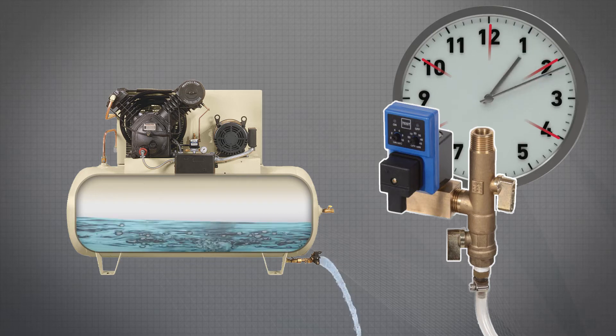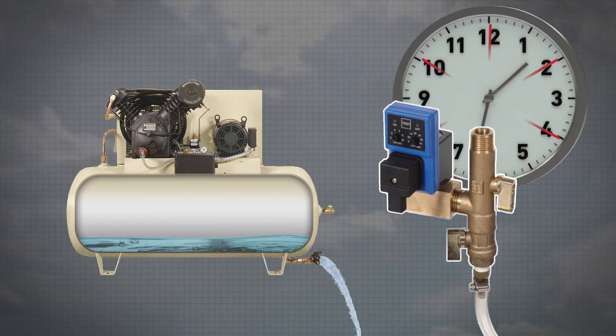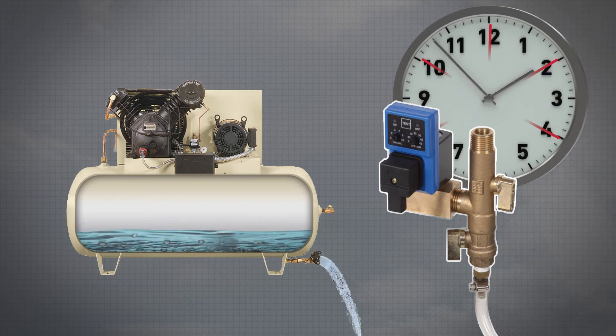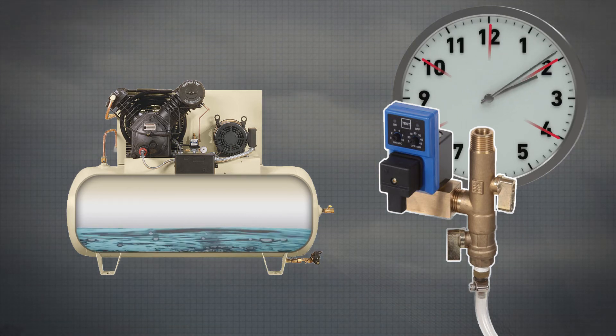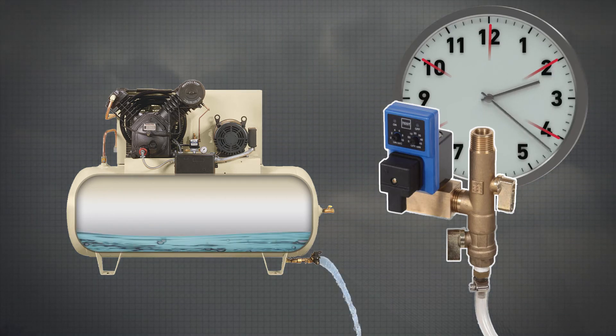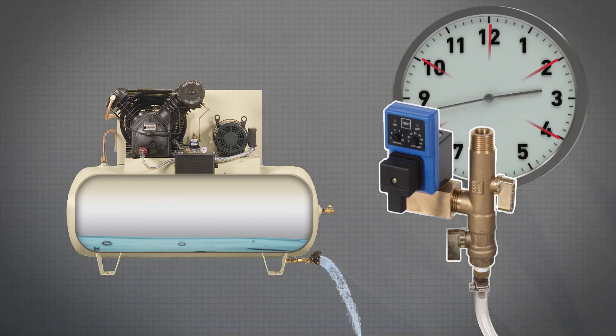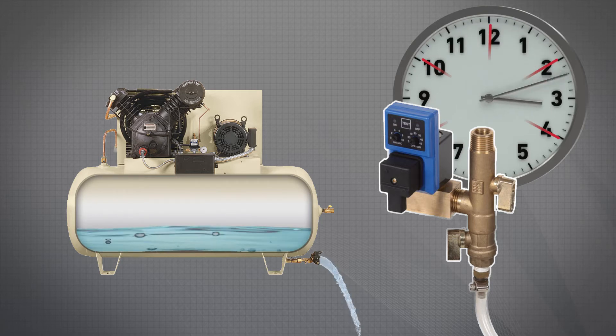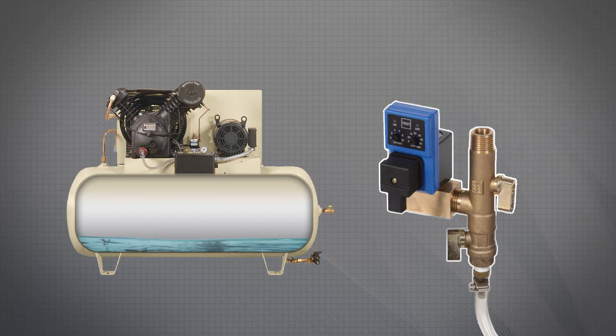The volume of condensate present in the expansion tank fluctuates with the amount of humidity in the air during compression, with pump cycles occurring through the day. A static, timed drain has no feedback related to humidity and cannot adjust the frequency or duration of the drain. Without any knowledge about condensate volume, the drainage cycles are either directly wasting money by unnecessarily opening the valve and lowering the internal pressure — causing the pump to cycle — or not expelling enough condensate, leading to undesired moisture in the lines. Neither of these is desirable.